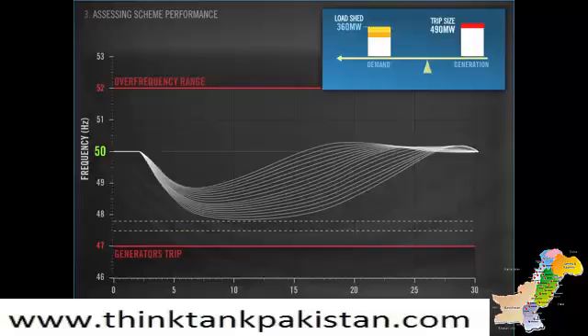The events being shown on the seesaw and graph are referred to as contingent events. To cover these events, we rely on purchasing interruptible load and generator reserves. This prevents the frequency from falling below 48 Hz and returns it to the normal range. These aren't really the events that we are concerned about with AUFLS. As soon as the frequency goes below 48 Hz, we are in AUFLS territory.